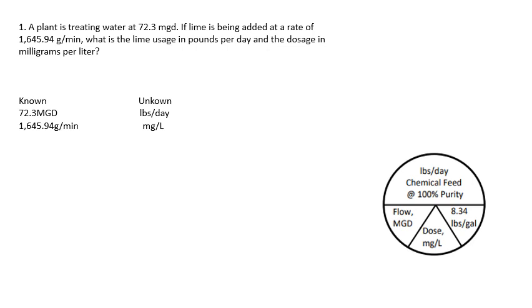These are a little bit more complicated than part 1. We'll start with our knowns and unknowns. What we know is that the flow is 72.3 million gallons a day and the dosage rate is 1,645.94 grams per minute. What we don't know is the pounds per day or the milligrams per liter. To get milligrams per liter, we're going to have to start with pounds per day.